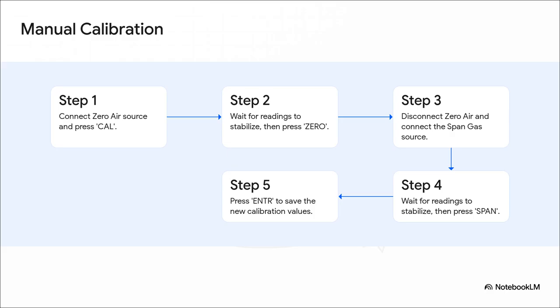Next, swap out the zero air for your span gas. And again, you gotta be patient, wait for those numbers to settle down. Then you hit span to set your high point. And the final, most important button press, hit enter to save it all. Don't forget that last step.